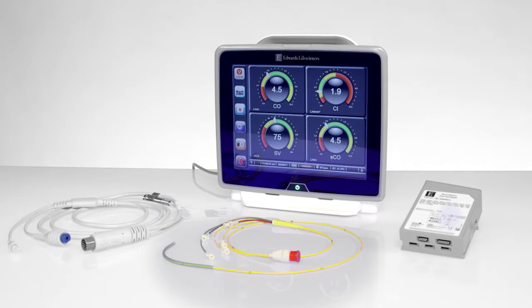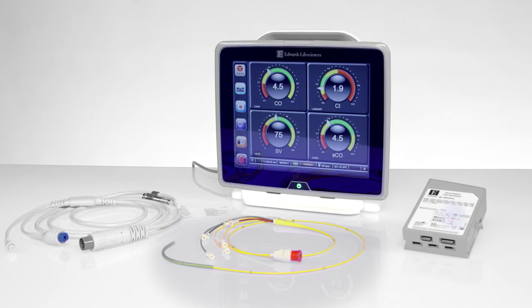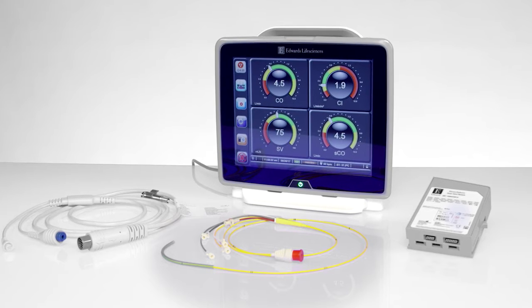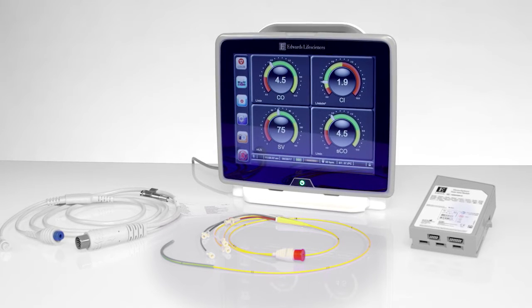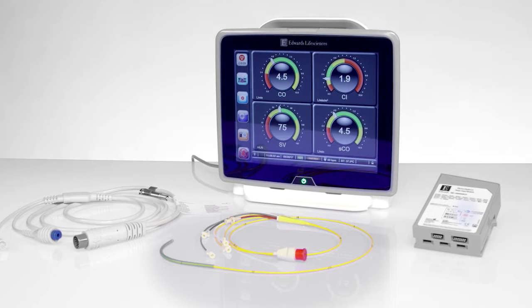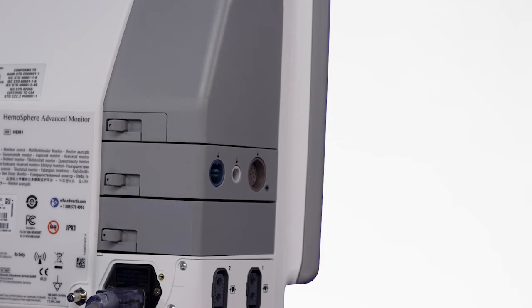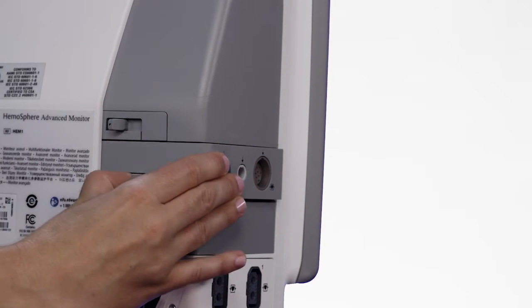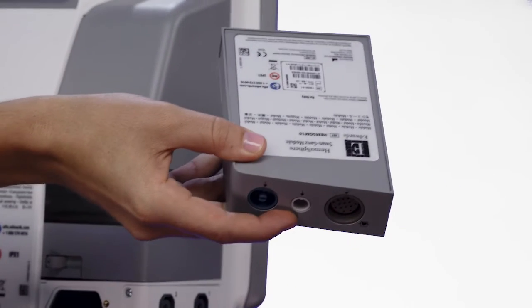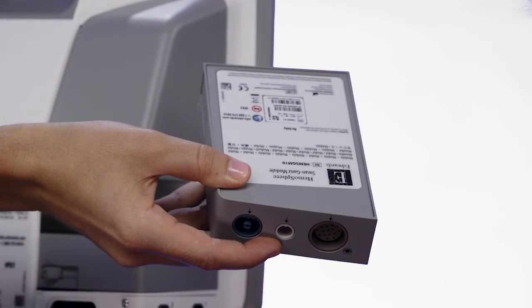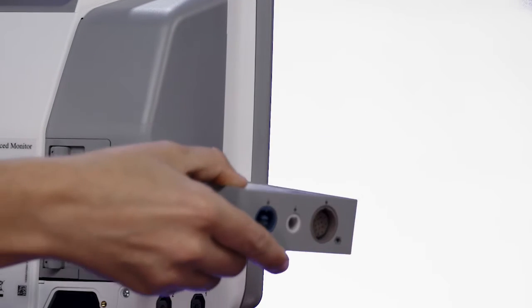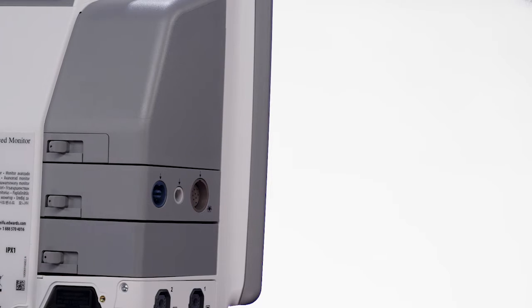The modular design of the HemoSphere Advanced Monitoring Platform allows you to tailor its use to your specific needs by installing instrument modules. To remove a module, press the release button and then slide the module to the right. Insert the desired instrument module into the empty expansion slot and slide to the left until it clicks into place.